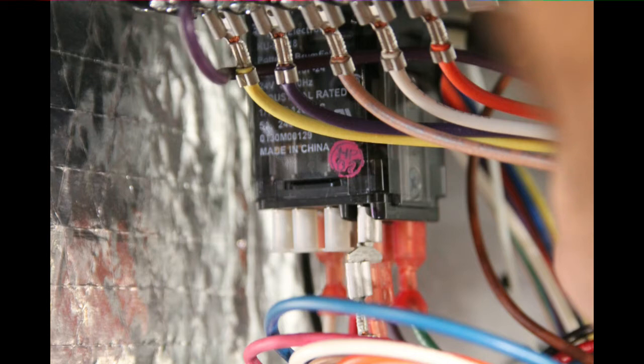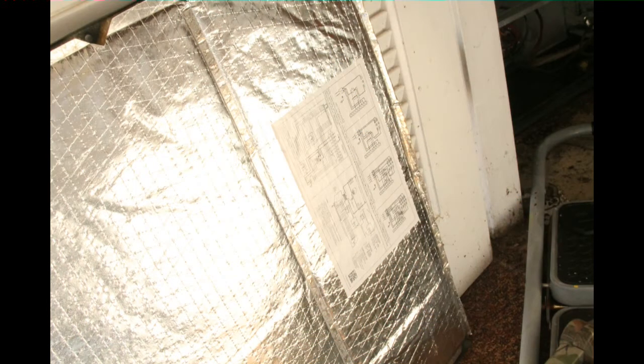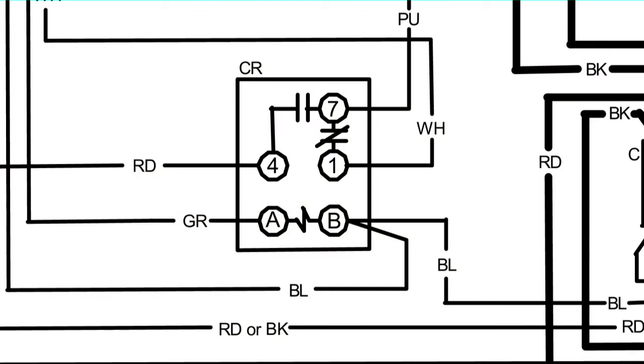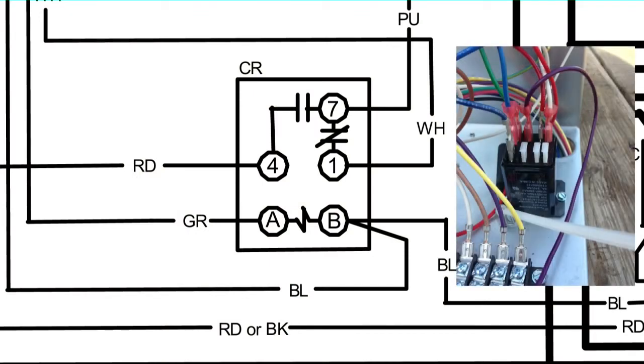Let's take a closer look at the wiring diagram and see what it looks like on the schematic. You can find the schematic on the back of the controls compartment door on the ASPT. As you look at the relay in the picture, you'll see down at the bottom you have an A and B with a squiggly little line in between them. That is the coil for the relay. It is a 24-volt coil, which means once you have power to that coil, your switching action will take place.